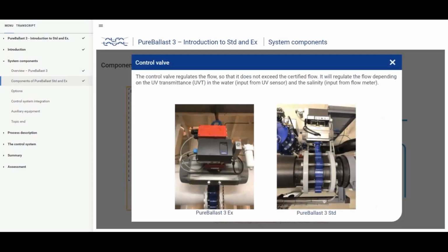The control valve regulates the flow, so that it does not exceed the certified flow. It will regulate the flow depending on the UV transmittance in the water, input from UV sensor, and the salinity, input from flow meter. The control valve also regulates the pressure during filter backflush, self-cleaning of the filter.